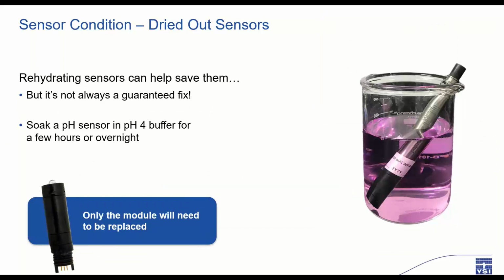If you discover that your pH or DO were stored dry, all may not be lost. We have a chance to revive them with rehydration. If the pH module was accidentally stored dry, you can try to rehydrate it by soaking it in pH buffer 4 for several hours or even overnight, and then attempting calibration. If the calibration fails after this rehydration attempt, then the pH module will likely be in need of replacement.